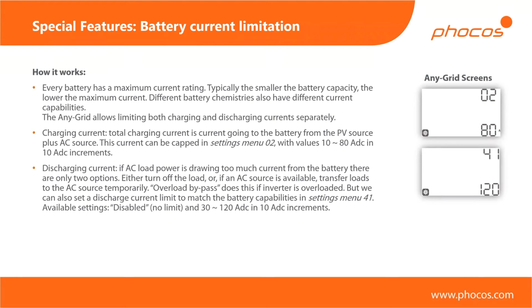Because if there's a tendency to take batteries which are almost too small for the system, then we need to figure out a way to get power from elsewhere so that we don't overload the battery. So in that case, basically the battery is too weak compared to the 5 kilowatt or 3 kilowatt, depending on what model you take, that you're trying to provide to your loads. So we have this split up into the charging and discharging current. The charging is relatively simple. Regardless of whether they're lead acid or lithium batteries, you'll find a maximum charging current. So let's say, for example, your maximum charging current is 40 amps for a particular example system.